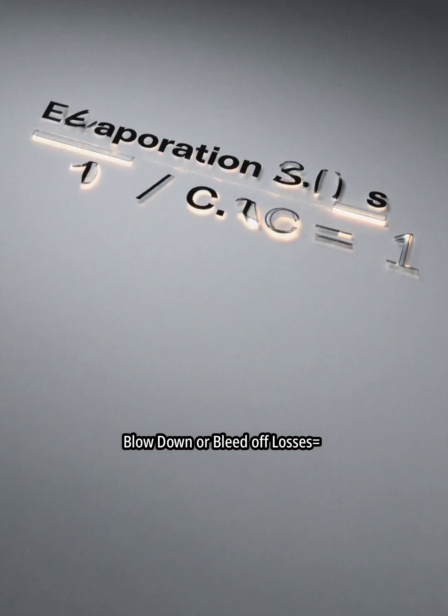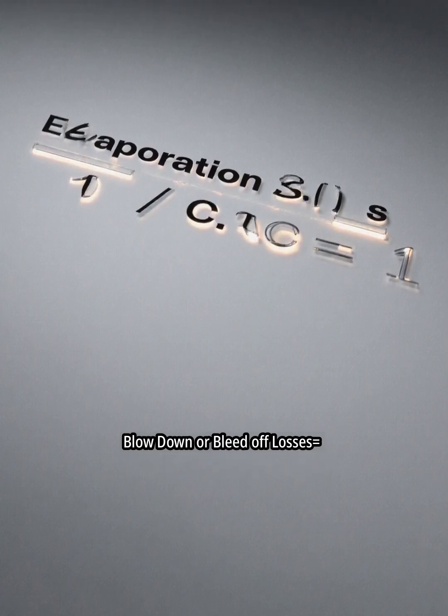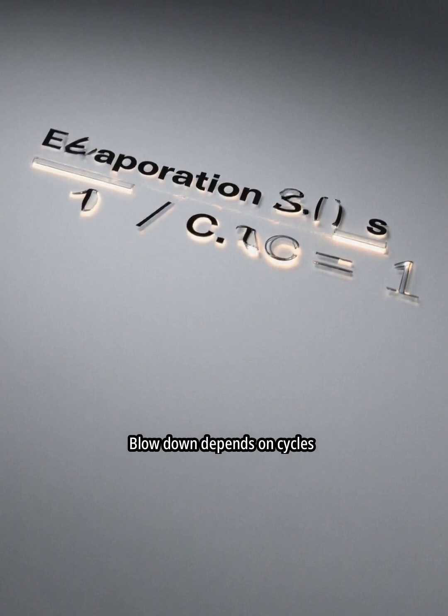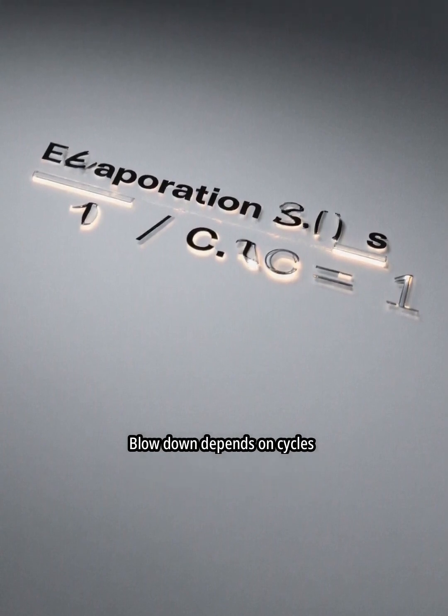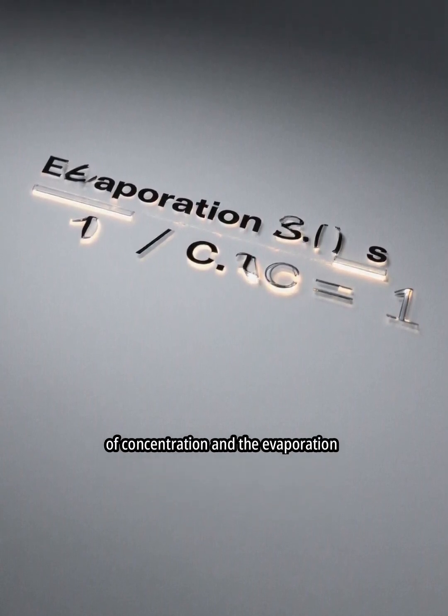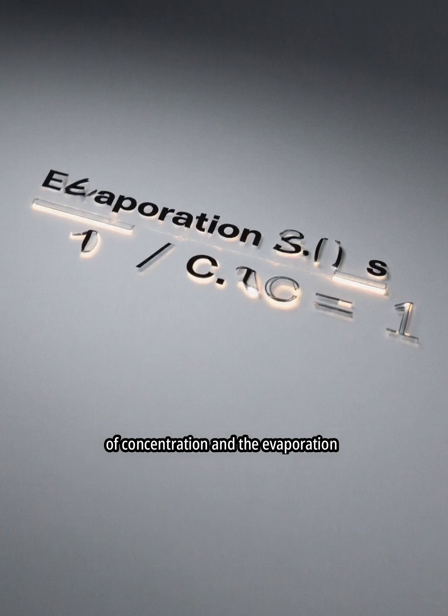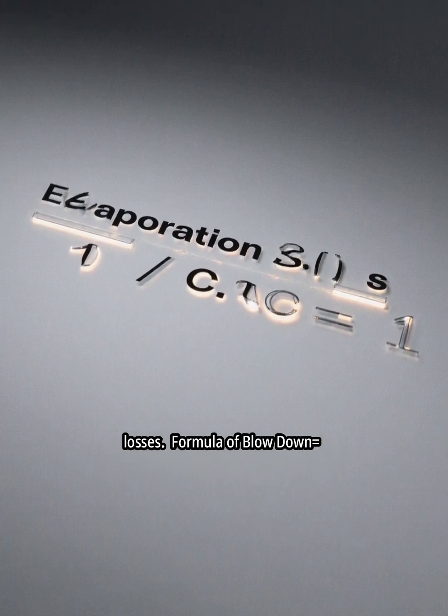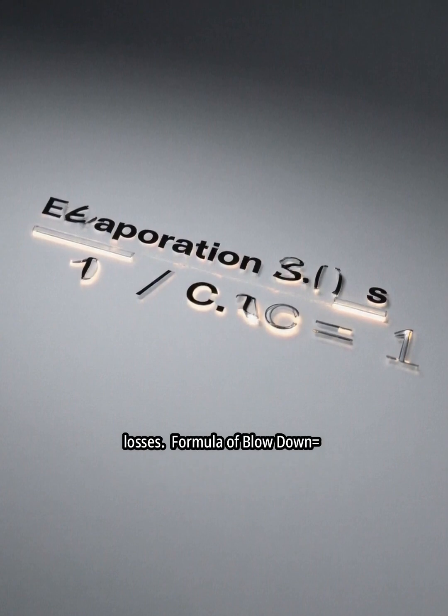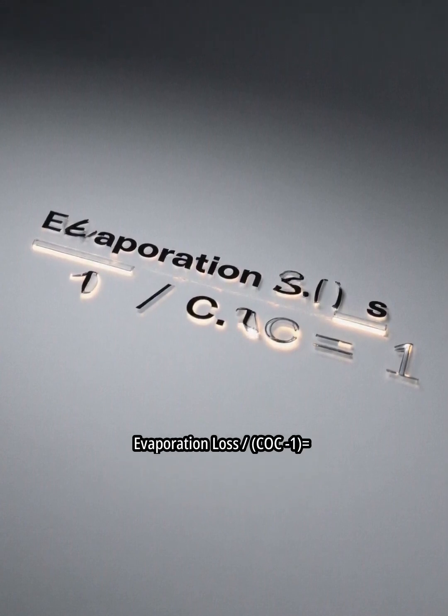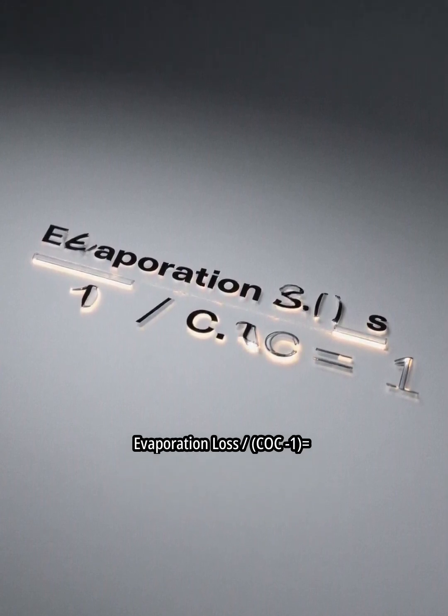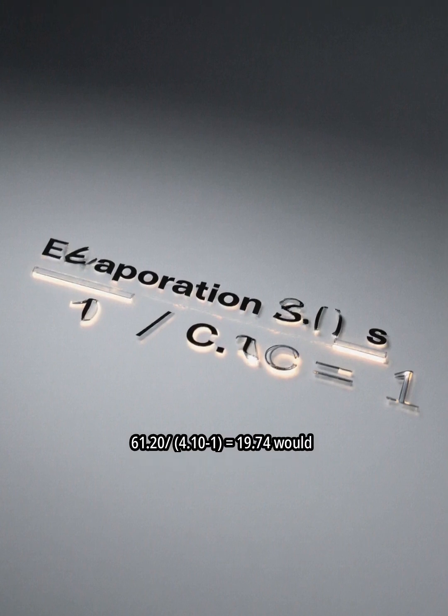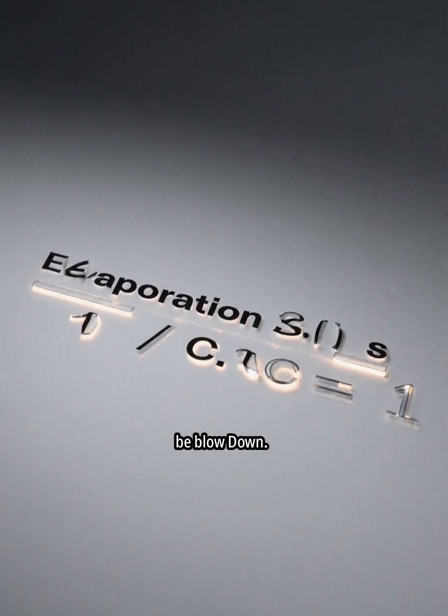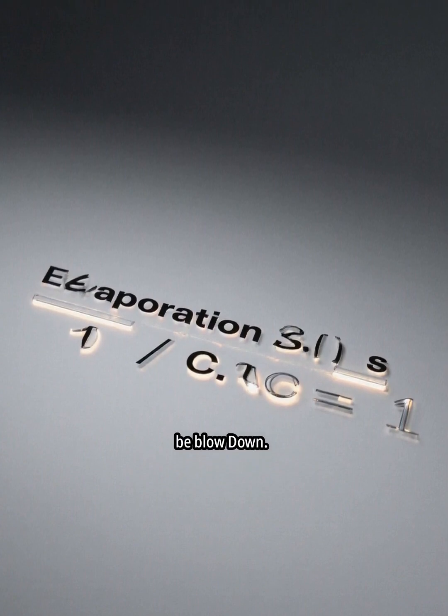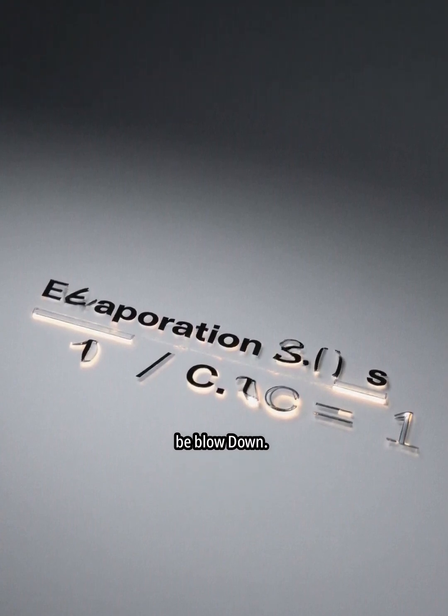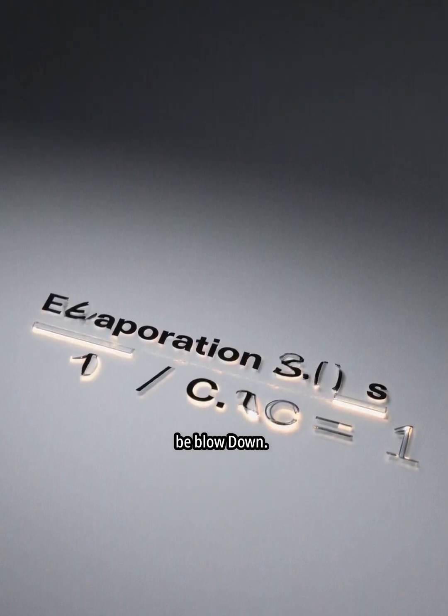Blow down or bleed off losses. Blow down depends on cycles of concentration and the evaporation losses. Formula of blow down equals evaporation loss divided by COC minus 1, equals 61.2 divided by 4.1 minus 1, equals 19.74 would be blow down.